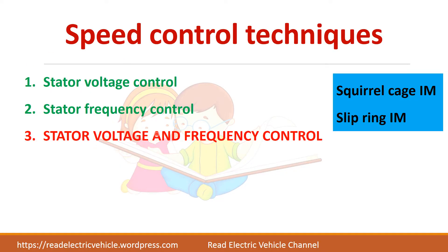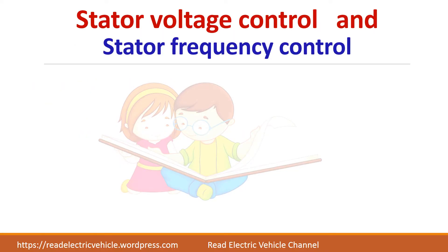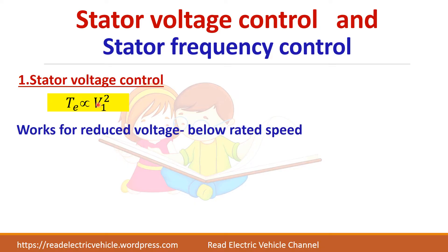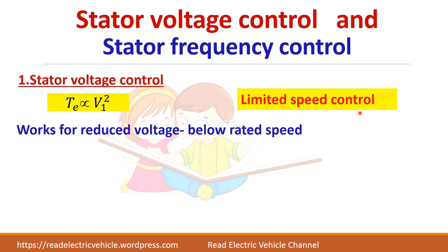These three techniques are applicable for both squirrel cage induction motor as well as slip ring induction motor. In stator voltage control technique, torque is directly proportional to voltage squared. By varying the stator voltage you are able to control the speed, but voltage can only be reduced — it cannot be increased beyond the rated value. So you can achieve speed control only below rated speed, which is a limited speed control drawback.